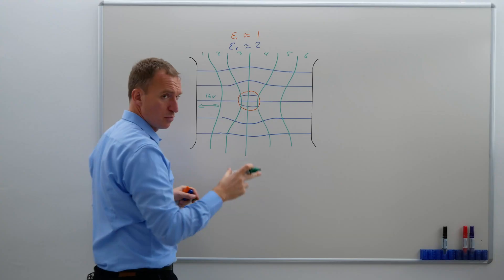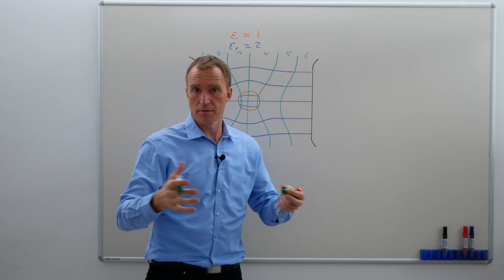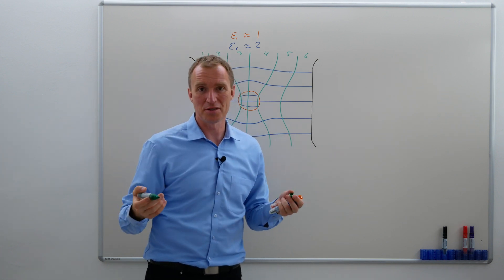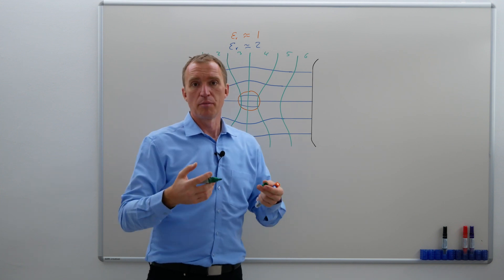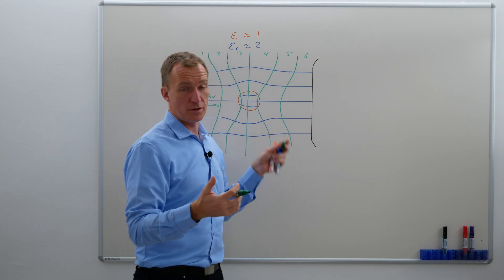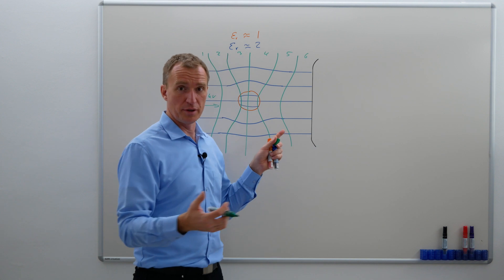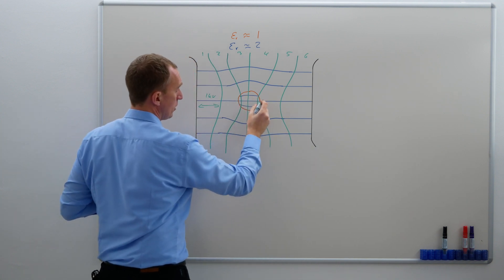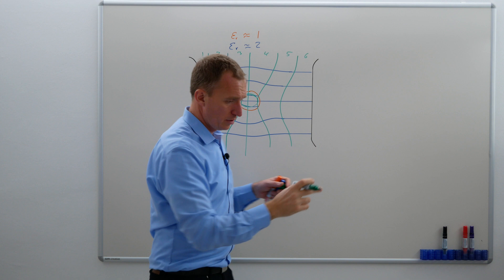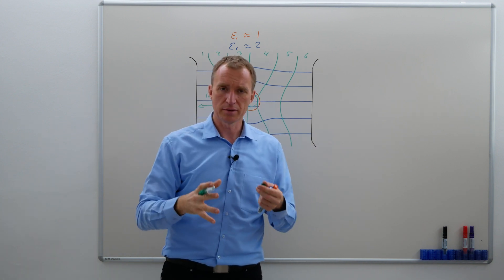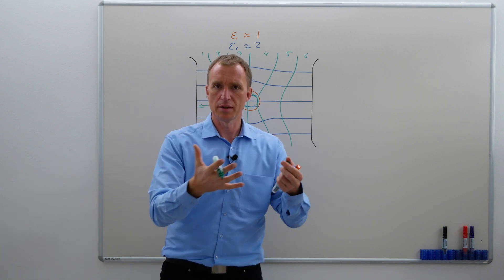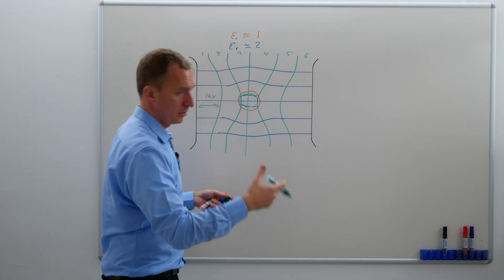Because in here this is the weakest point, this is our air, this is our gas, let's say it is air, epsilon_r of 1 more or less. So this is the weakest point already in our insulation system, because the partial discharges will start at a much smaller kV per millimeter value than in the solid insulation material. However, in this point, from here to here is 1 kV, from here to here, meaning in this from here to here is already 2 kV.